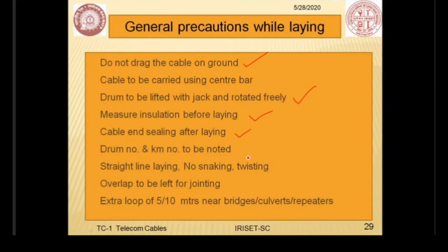If you leave the end of the cable open, or if any cable in between is punctured, water can potentially enter from there and travel by gravity to the vulnerable location of the joint, where you can find accumulation of water. This is what we practically observe in the field.